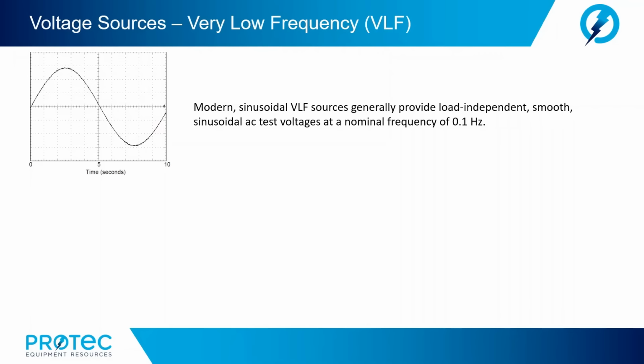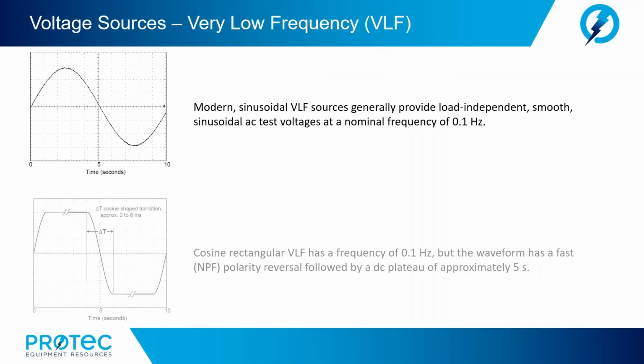Now, modern sinusoidal VLF sources generally provide load-independent, smooth sinusoidal AC test voltages at a nominal frequency of 0.1 Hertz. The cosine rectangular VLF has a frequency of 0.1 Hertz, but the waveform has a fast near power frequency polarity reversal followed by a DC plateau of approximately 5 seconds. So in essence, we get 5 seconds of positive DC, a near power frequency polarity transition, followed by a plateau of 5 seconds negative DC.